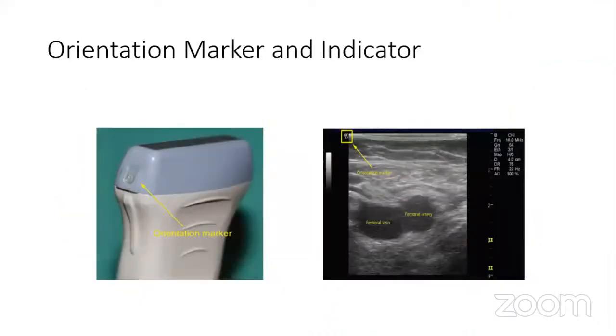Now, whatever probe you use, you have to see where the orientation marker of the probe is, because it corresponds to the orientation indicator on the screen. So whenever you are using your probe, just see where the orientation marker is and where the orientation indicator is on the screen. This is very, very important. Otherwise, you will not be properly oriented and you'll be in trouble. You will not identify the structure properly.